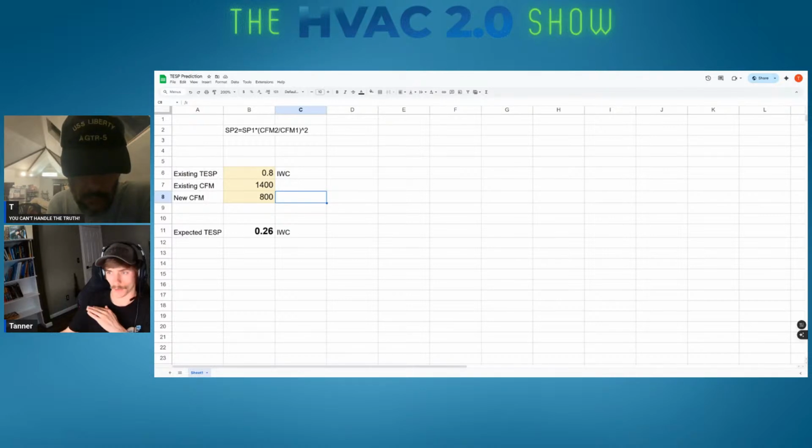like, what does that typically look like? Because there's so many different variables and you want to kind of isolate that to go, okay, here is PSC motors, and here's a slew of data from that. Here's PSC motors with a dirty blower motor, befores and afters, EC motors before and after, all these types of things.